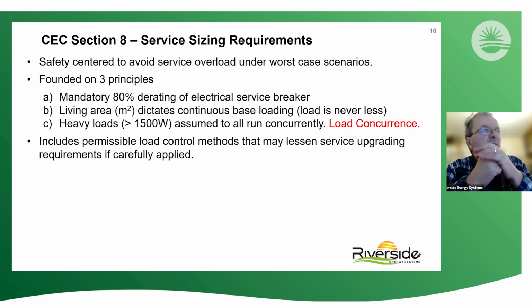And that's dictated strictly by the living area of the building, not by actual loads. So that ends up being quite punitive, as we'll see in a moment. And then the third concept is that any heavy loads in excess of 1500 watts are assumed to all run at the same time. In other words, we assume load concurrence. So as I mentioned, this leads to a worst case scenario. Now, there's also permissible load control methods in Section 8 that can help us lessen service upgrading requirements if we apply them carefully. And sometimes those are overlooked. So we're going to look at those a bit here in a couple of minutes.